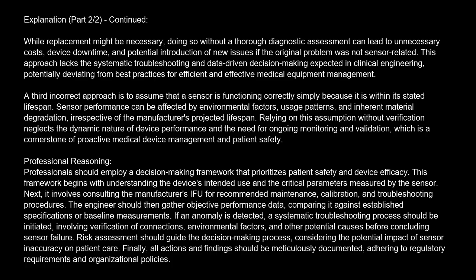A third incorrect approach is to assume that a sensor is functioning correctly simply because it is within its stated lifespan. Sensor performance can be affected by environmental factors, usage patterns, and inherent material degradation, irrespective of the manufacturer's projected lifespan. Relying on this assumption without verification neglects the dynamic nature of device performance and the need for ongoing monitoring and validation, which is a cornerstone of proactive medical device management and patient safety.